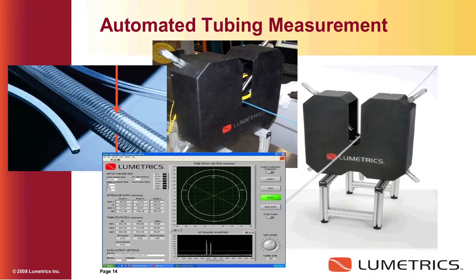We've also done online work — we've done online for catheter extrusion and we have this system at our booth. We've done online for high-speed glass tubing extrusion up to 1,400 feet per minute with single and multiple probes. When you have multiple probes in that one particular device, you can pick up more data. That's pretty straightforward now that we've had lots of experience in the field doing it with customers.